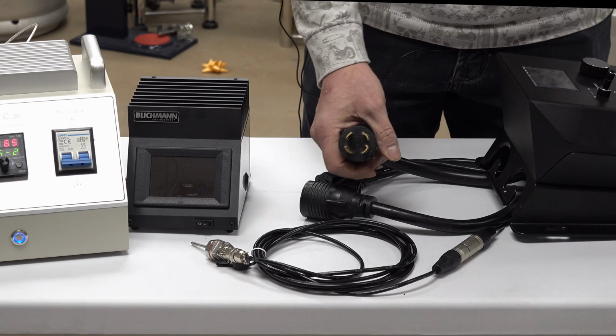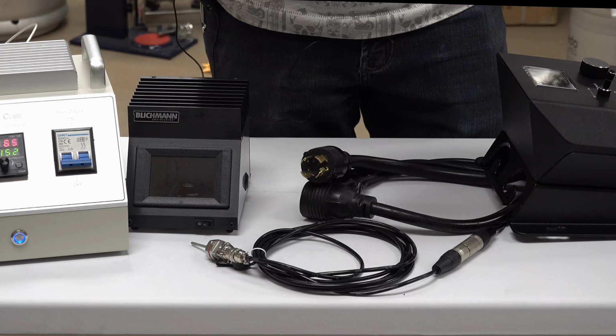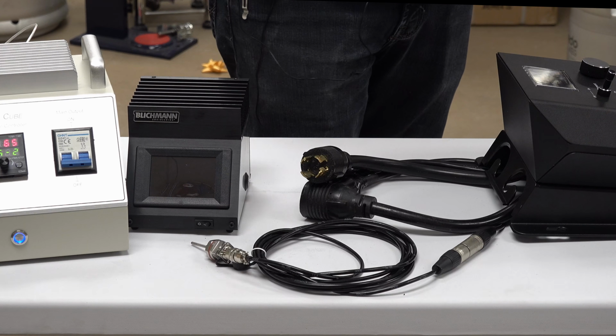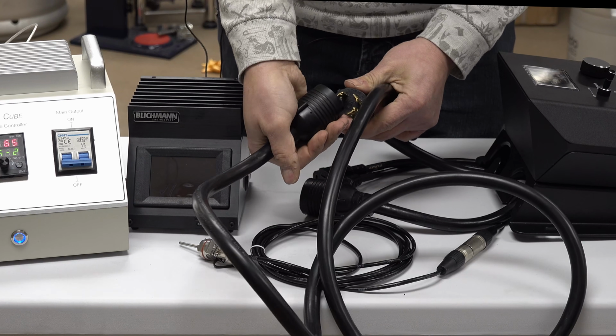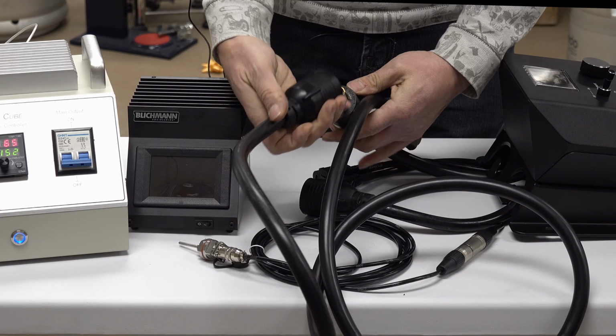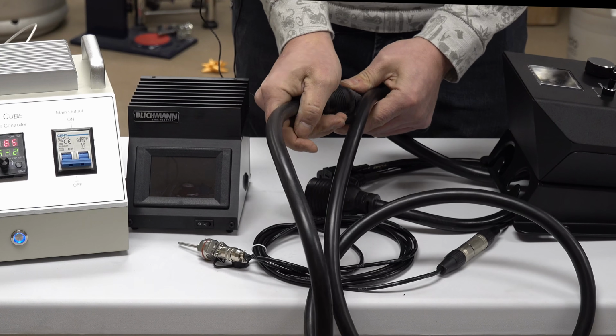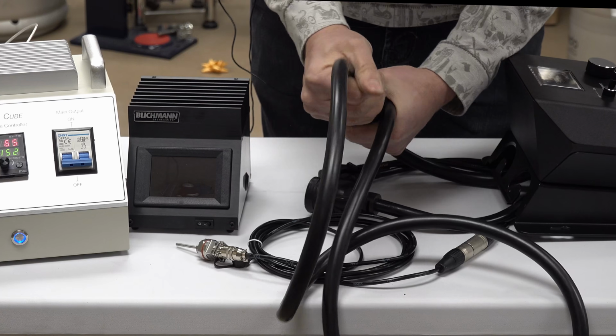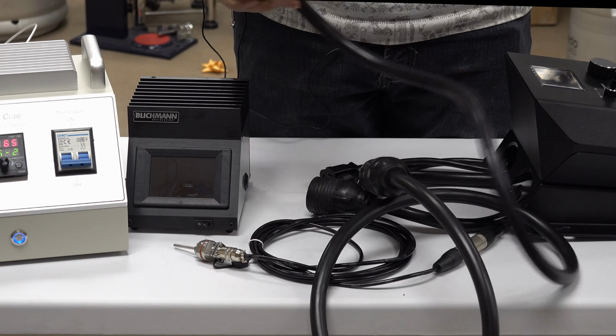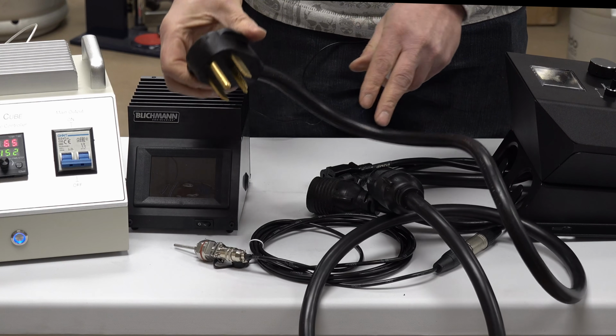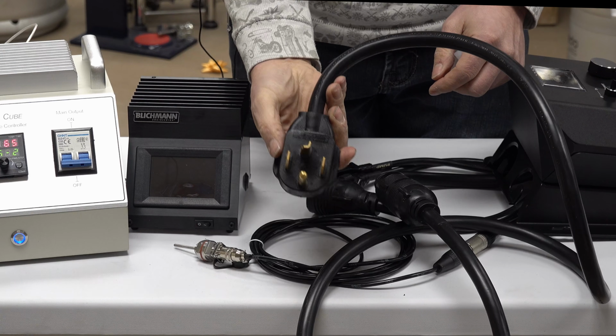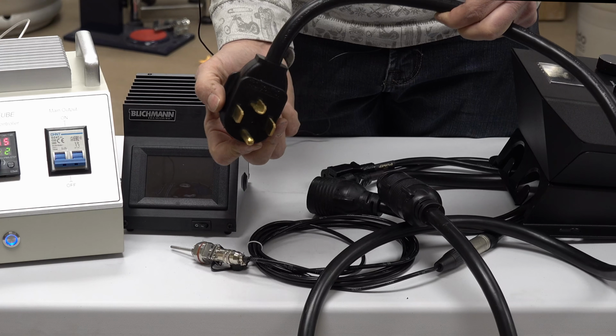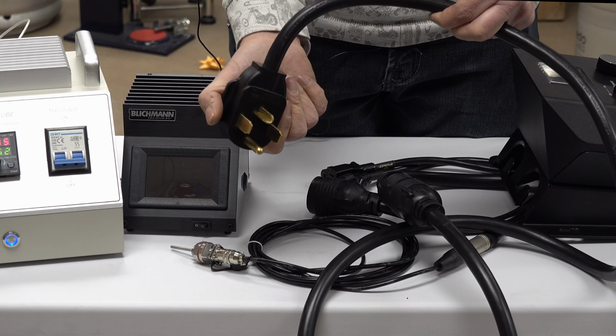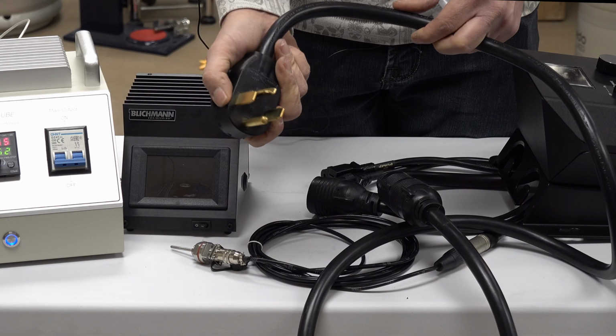They supply a cable that's about 6 feet long, and you attach this twist lock - an L14-30 R and P joint - and then they have a straight bladed plug that goes into your wall. That's how it gets 240 volts and 120 volts on the same cable.